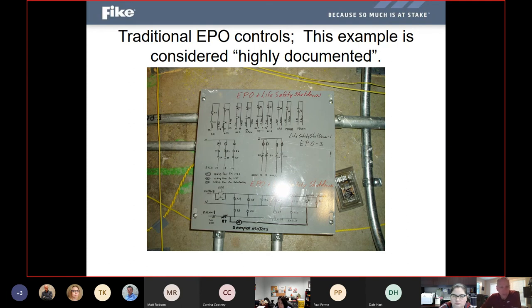Here's an example of something that might be considered highly documented just because somebody actually took the time to sketch out on the cover box of that electrical box what's tied into what and how things are wire nutted together. But still, that would make somebody very nervous to take that cover off and try to either bypass something or add something to it, because the last thing anybody wants is their lights to go out and their servers to go down in a computer room because somebody inadvertently tripped the EPO system or circuit.